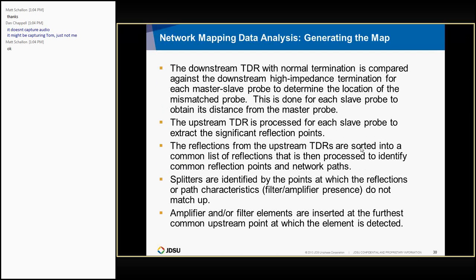Okay, the process of generating the map, this is where things get a little tricky. The downstream TDR with the normal termination is compared against the downstream high impedance termination for each master-slave probe to determine the location of the mismatched probe. That's done for each slave probe to determine its distance from the master. The upstream TDR is then processed for each slave probe to look for significant reflection points along that path. Reflections from the upstream TDRs are sorted into a common list of reflections that is then processed to identify common reflection points and places where splitters would occur. I'm going to explain this quickly and move to the examples because I think the examples do a much better job of showing what's going on.